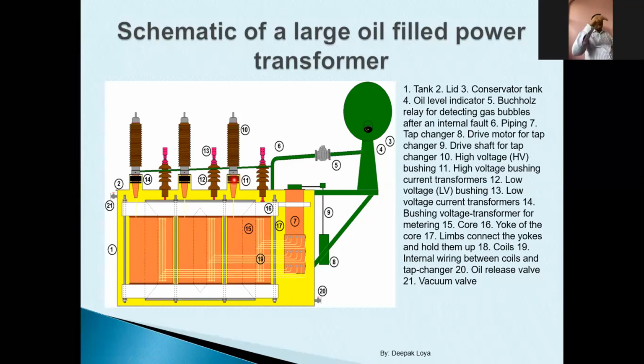And if 5000 ampere current is flowing through that bushing or the transformer, I will be getting a 1 ampere signal at the secondary of my CT. So if the current becomes 6000, then my CT will read 1.2 ampere. If my CT is reading 1.2 ampere, that means my transformer is operating at 20% overload. Whether my transformer can handle that 20% overload or not, I know, because when I designed the transformer I knew whether it can handle it or not. And depending on that, we will have our operating relay mechanism. On my relay, I will set whether it can handle 10% overload or 20% overload, or whether 20% overload should be treated as a faulty condition and my transformer should be taken out of operation. So there is a requirement of a CT for that purpose.